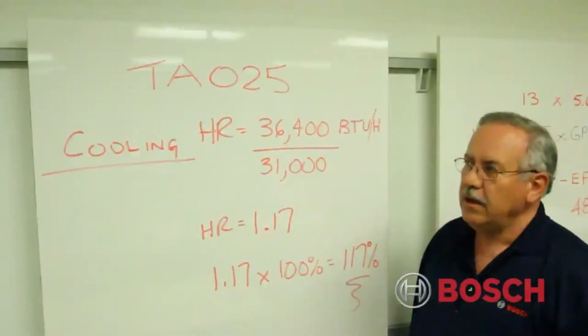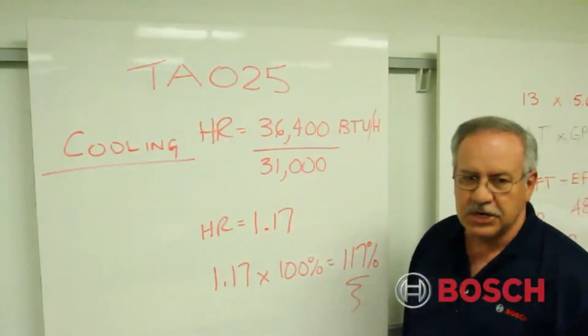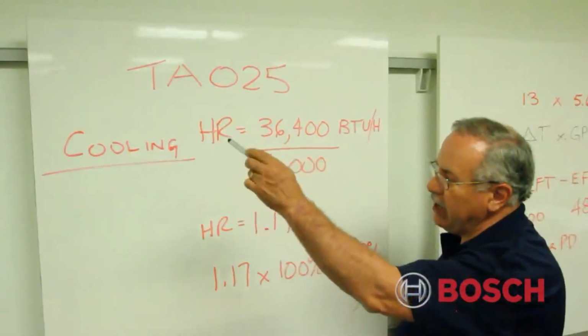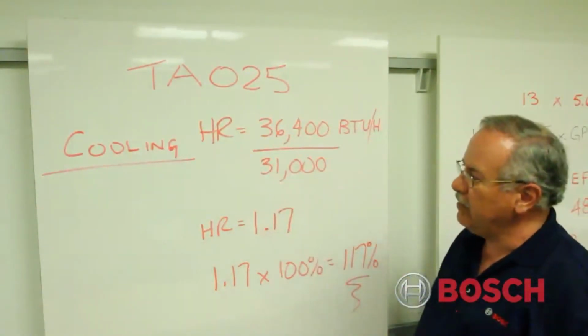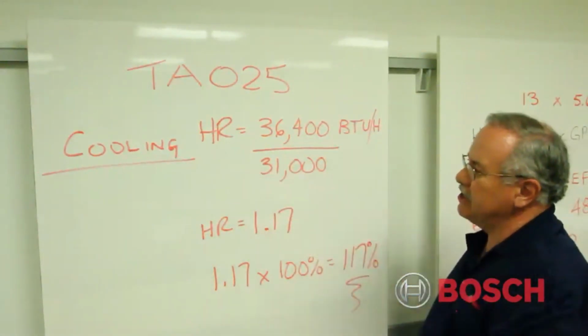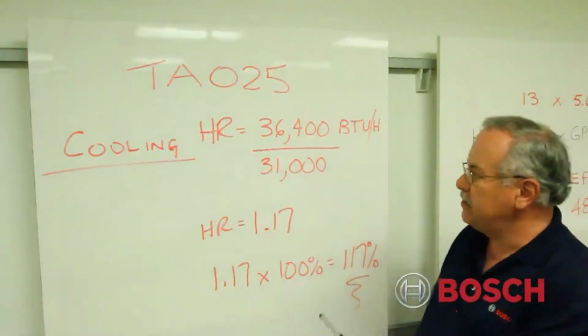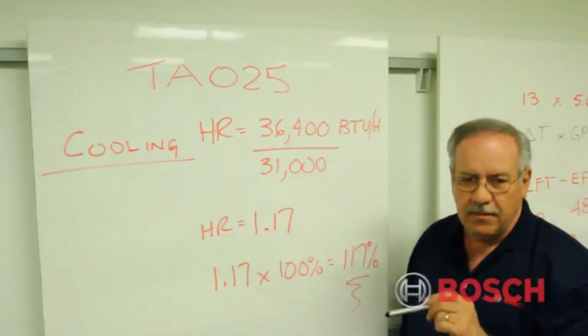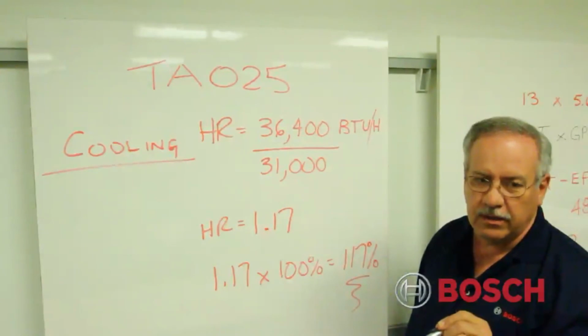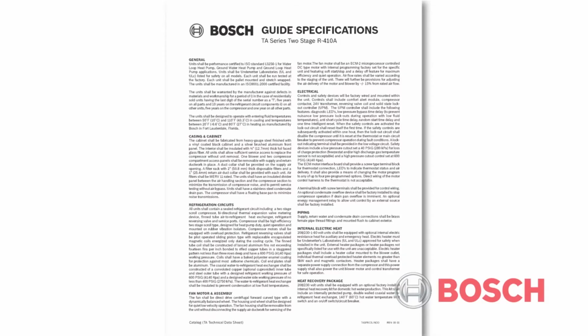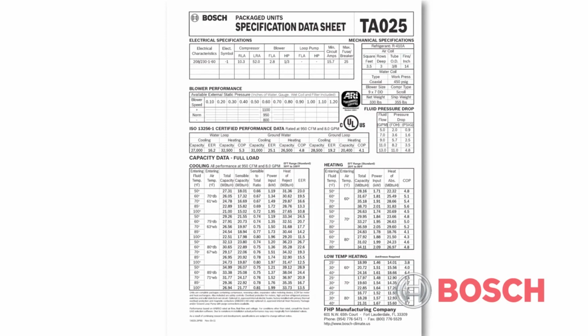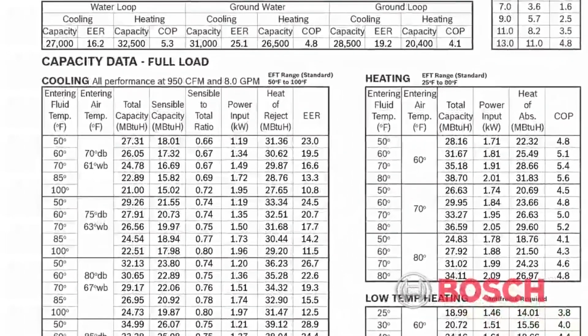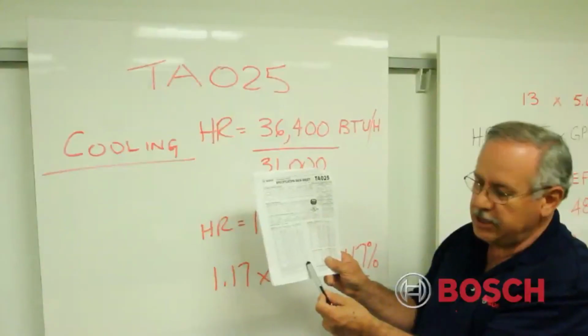into the earth. Now the final step in determining the heat of rejection in this particular case, remembering that we have a TA025 and we're operating in the cooling mode, what we have calculated is approximately 36,400 BTUs per hour is being rejected based on our conditions at this particular location. Now we go to the specification data, which I referred to earlier, and down here on the lower right of the TA025 page, in full load is capacity data, full load cooling. One of the columns is labeled heat of rejection, MBTUH, thousands of BTUs per hour.